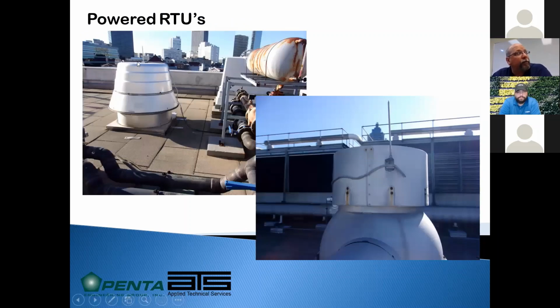Powered rooftop units with mushroom fans, as long as this fan is less than 4 foot in total diameter, we can have just a single one on top because we're within 2 feet of the edges. But the air terminal needs 2 paths to ground. They allow up to an 8 foot dead end. So if this total length of cable joins with the main roof conductor and it's not more than 8 total feet, this would be allowable. This one was over, so it actually needs a second path.